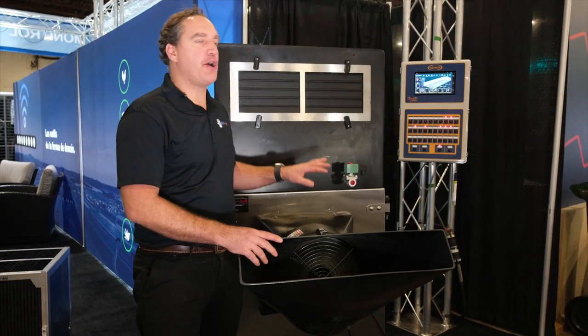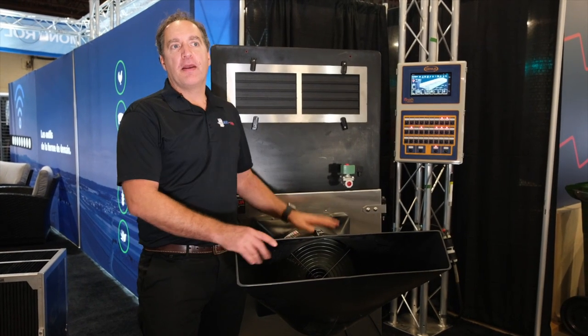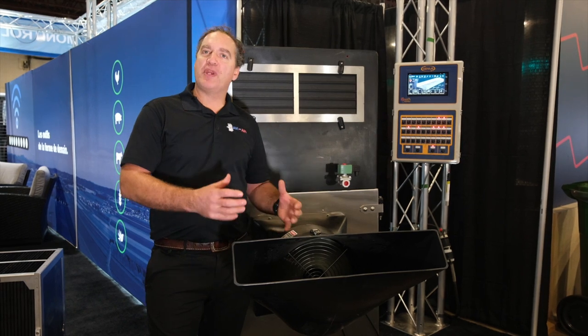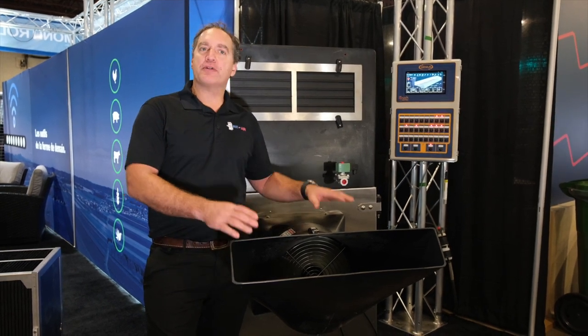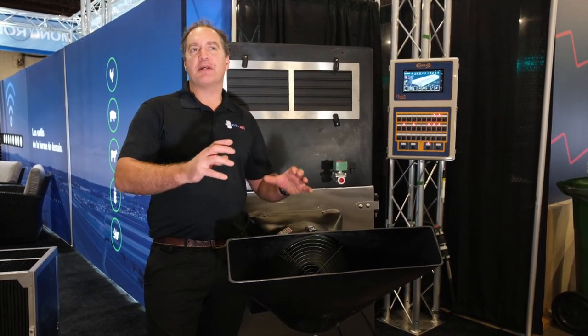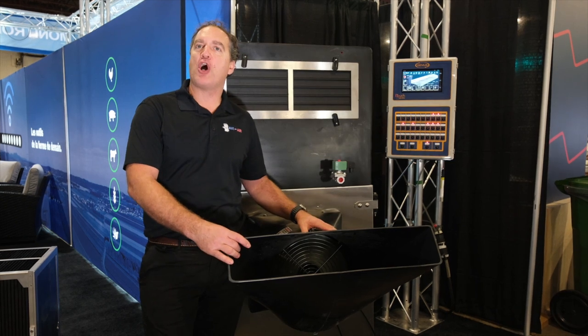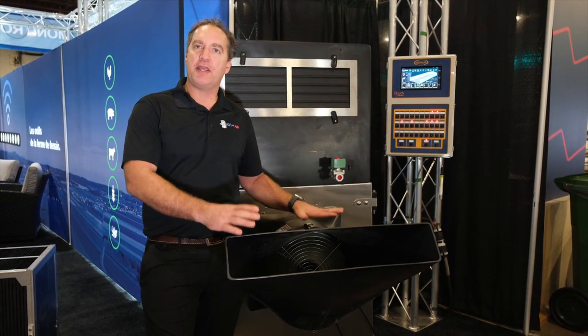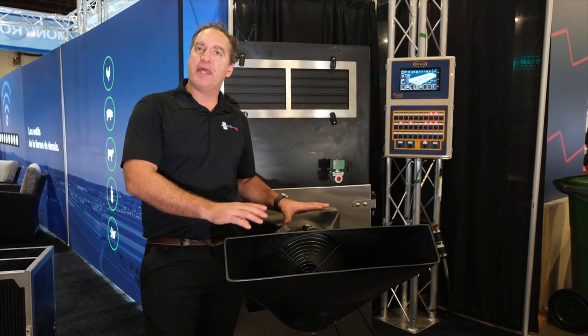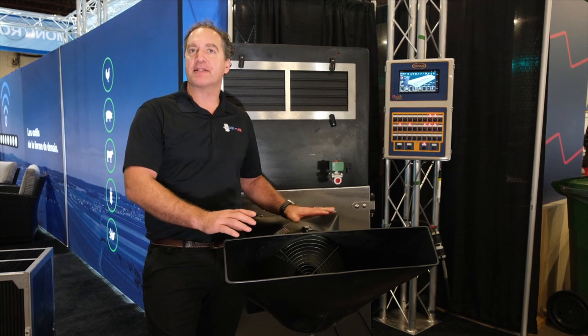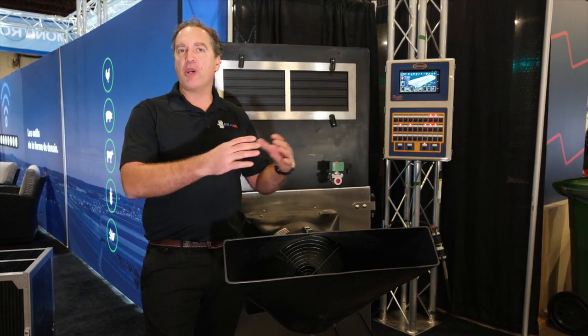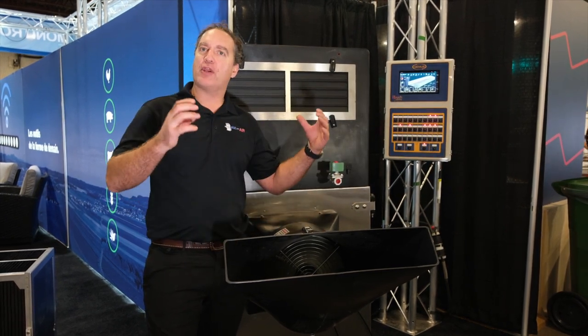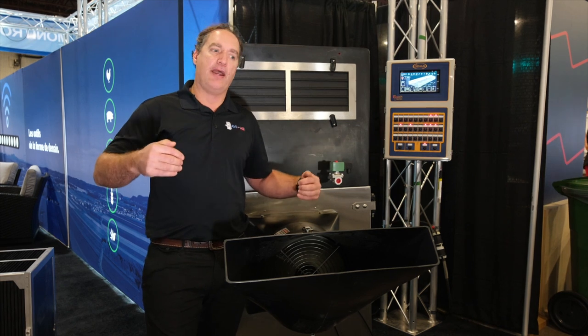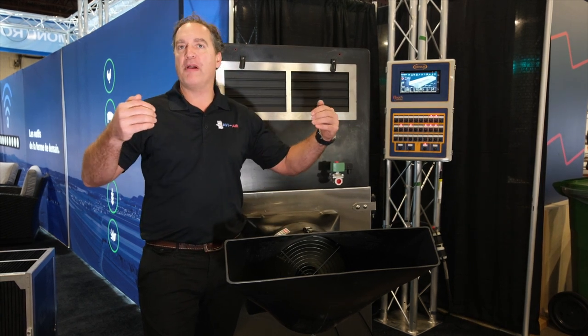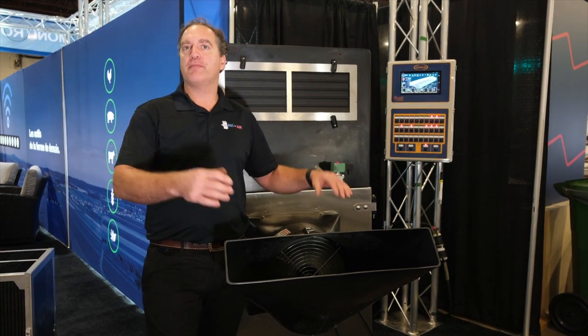Both fans are 1500 CFM each, and the average heat recovery that we've obtained throughout many years and in many situations is roughly around 50% of your heating cost that will be reduced with a heat exchanger, if you maintain your minimal ventilation up to 21 days with this system. And after 21 days, you have other standard regular fans that will kick in and bring more air to your building in addition to the heat exchanger.